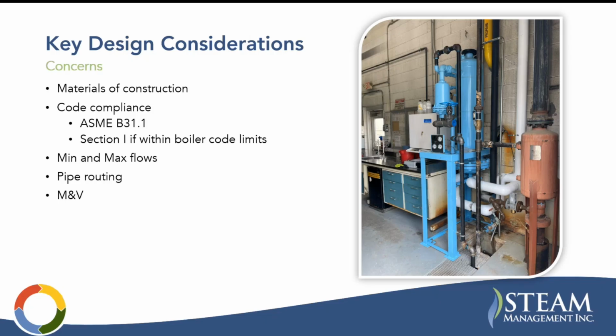So when you're thinking about it as an energy conservation measure, you're really smoothing that flow out, but you do need to consider what the maximum flow will be to the tank and how much it can handle. The pipe routing is always part of the equation. Sometimes boiler room layouts are different. As I mentioned, you have to connect to all those different pieces of equipment, so you have to run pipe to all of them, and what's the best location to put the thing in to minimize costs. These projects, I would say, most of the cost is in the piping installation and not in the unit itself. So that's always an interesting part of the puzzle.